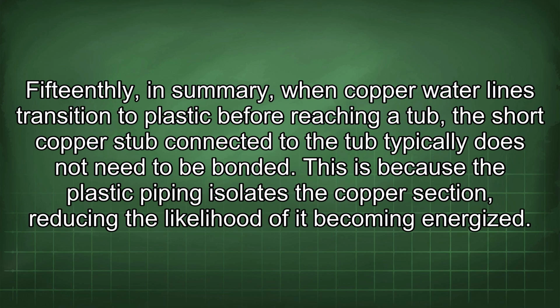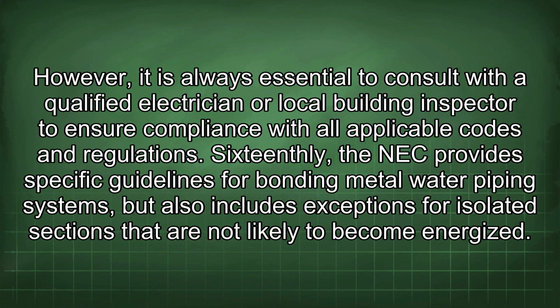Fifteenthly, in summary, when copper water lines transition to plastic before reaching a tub, the short copper stub connected to the tub typically does not need to be bonded. This is because the plastic piping isolates the copper section, reducing the likelihood of it becoming energized. However, it is always essential to consult with a qualified electrician or local building inspector to ensure compliance with all applicable codes and regulations.